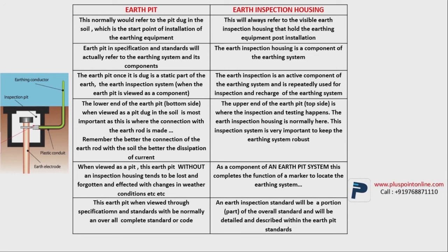Imagine you have created earthing without the earth pit and the earth inspection housing. You will find your earthing rod at some different place with your wires hanging strangely. Maybe someone has cut your wire, or due to some construction, the plates have disappeared. To avoid such situations and to maintain the earthing system, we developed the earth inspection housing system. The last difference between them is that the earth pit is developed with specific standards and conditions, whereas the earth inspection pit is developed depending on the specification of the earth pit. I hope you have understood the difference between the earth pit and earth inspection housing.